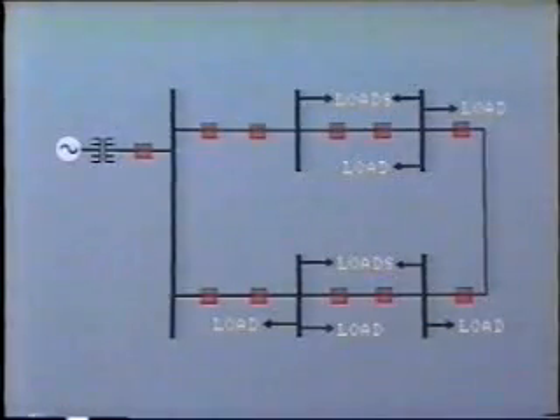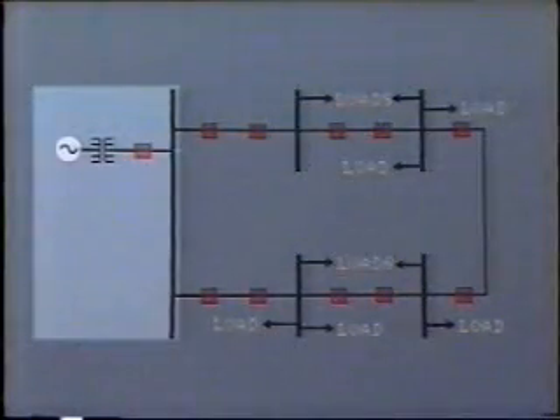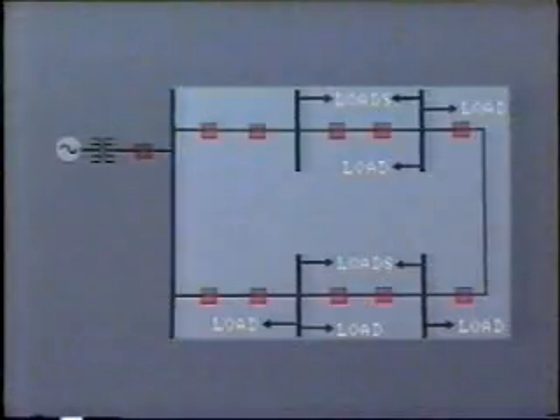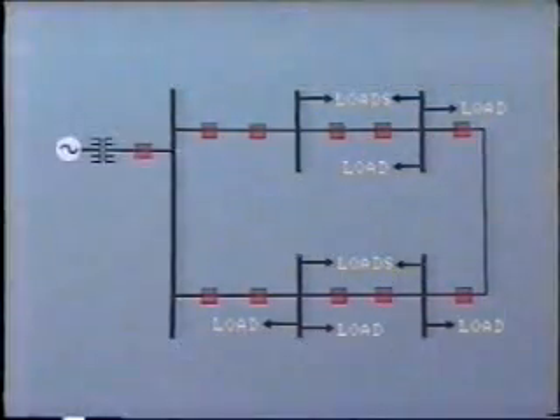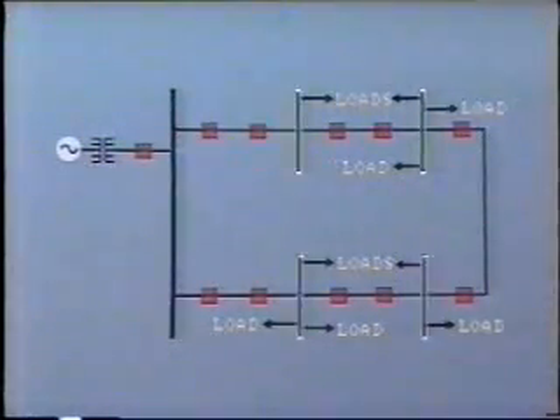The sub-transmission line may be connected radially, that is, one line to supply one distribution substation, but more commonly it is connected in a loop arrangement like this. Here we have one source of supply feeding into a loop which may cover a total distance of, say, 50 miles. At various points around the loop, distribution buses are located.